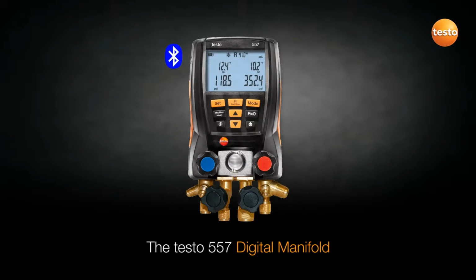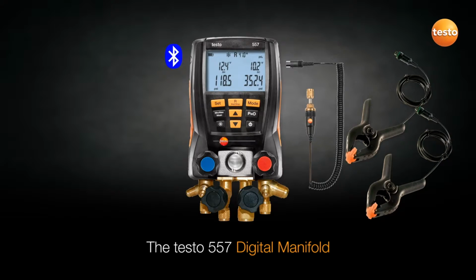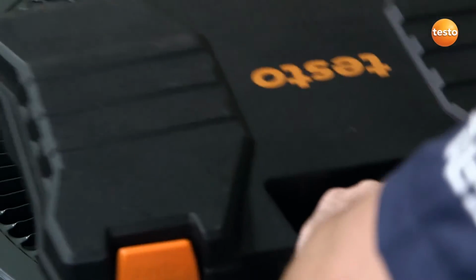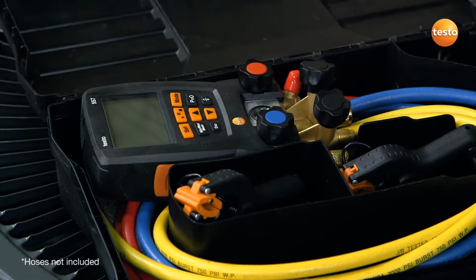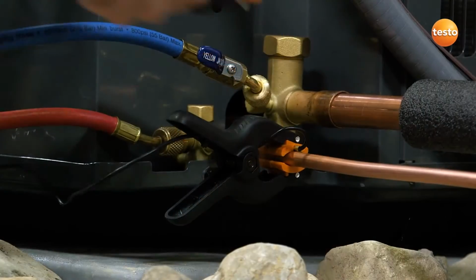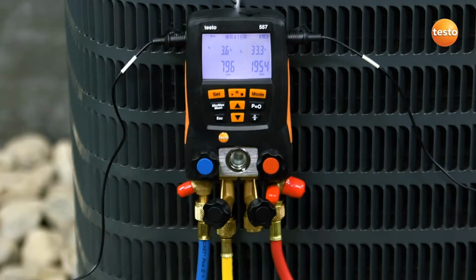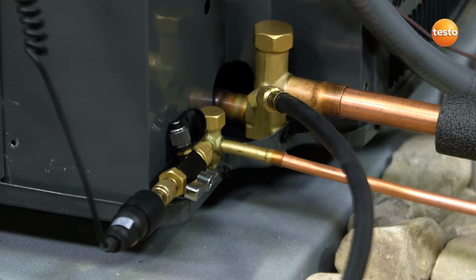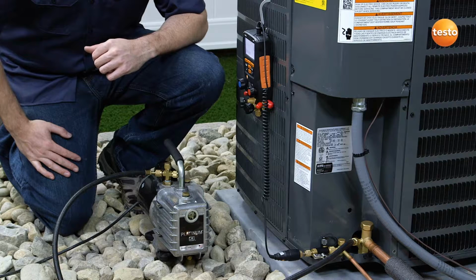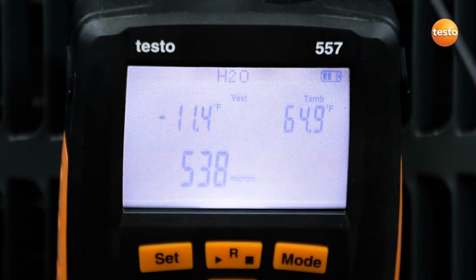If full system servicing is required, Testo's 557 digital manifold is a smart choice. The Testo 557, offering Bluetooth, 4 valves, and an external vacuum probe, means it is ideally suited for full system service. After connecting to the system, the 557 instantly begins to calculate evaporation and condensation temperatures, as well as superheat and subcool measurements. The external vacuum probe can be directly connected to the system, eliminating the need for pulling vacuum through hoses and manifold valves, providing faster and more reliable evacuations.